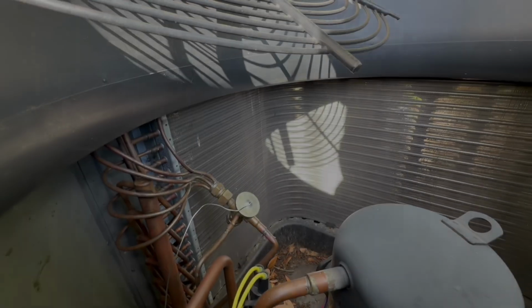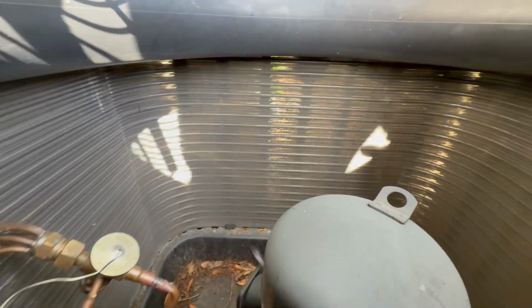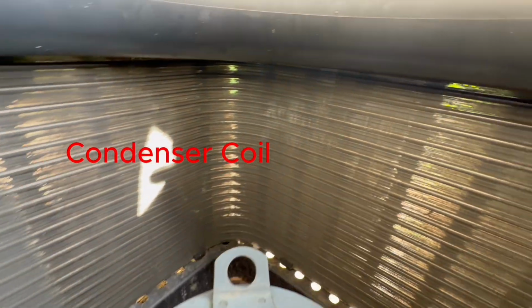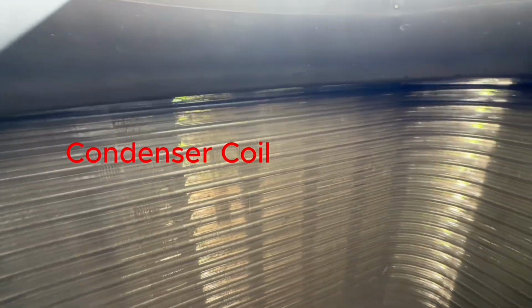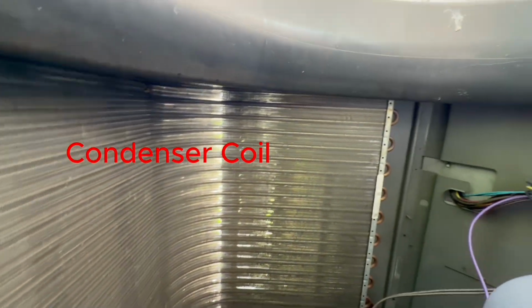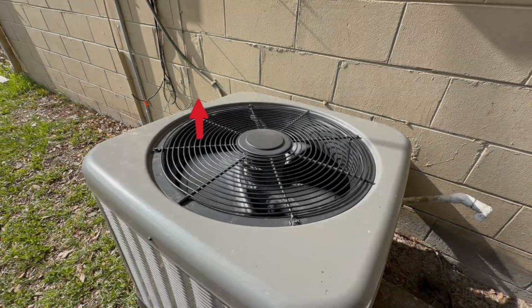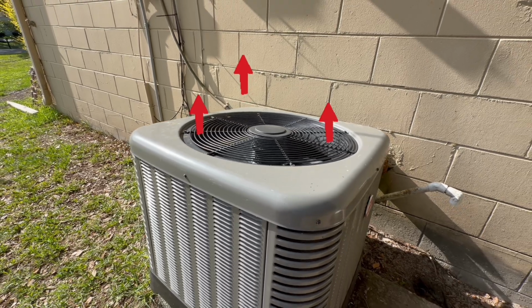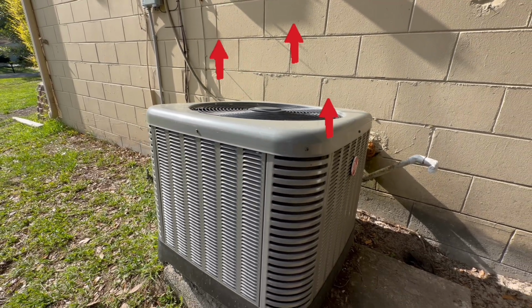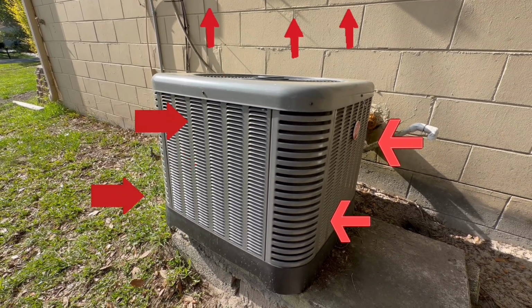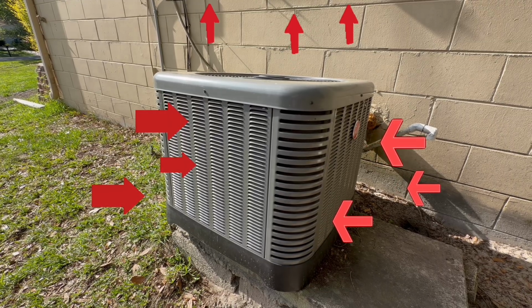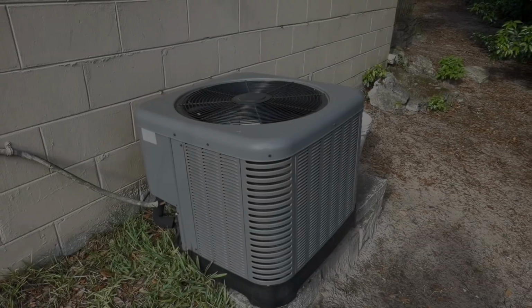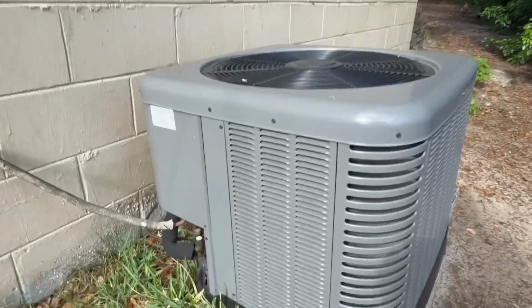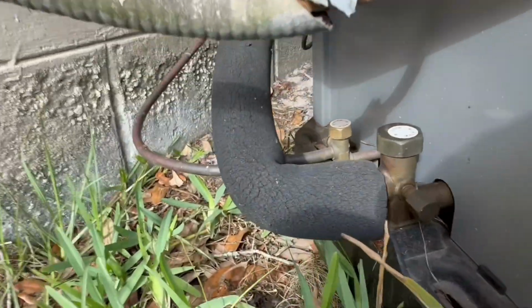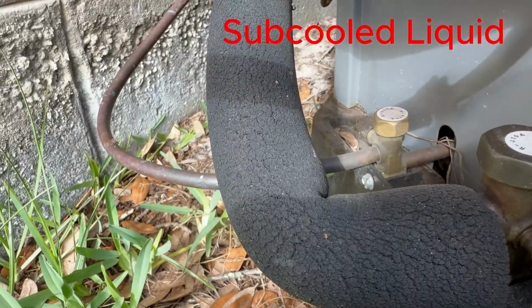Once the refrigerant has been discharged from the compressor, it then enters the condenser coil. The condenser coil is usually wrapped around the outdoor unit and is designed to remove heat. The condenser fan facilitates drawing air across the outdoor or condenser coil to accommodate heat removal. Once enough heat has been removed, the discharge from the outdoor unit will be subcooled liquid.